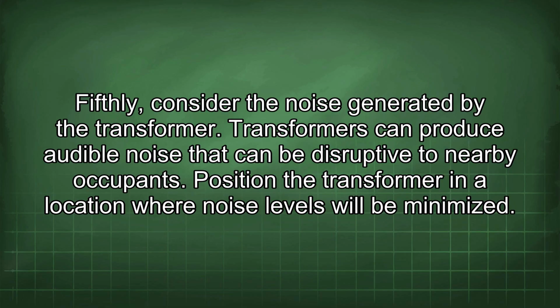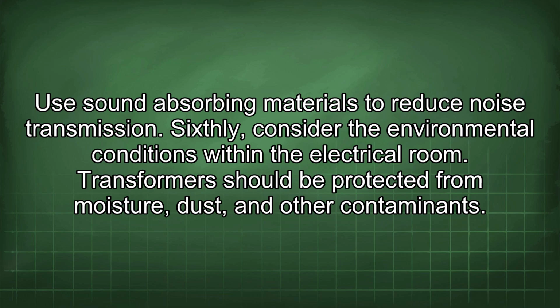Transformers can produce audible noise that can be disruptive to nearby occupants. Position the transformer in a location where noise levels will be minimized. Use sound-absorbing materials to reduce noise transmission. Sixthly, consider the environmental conditions within the electrical room.